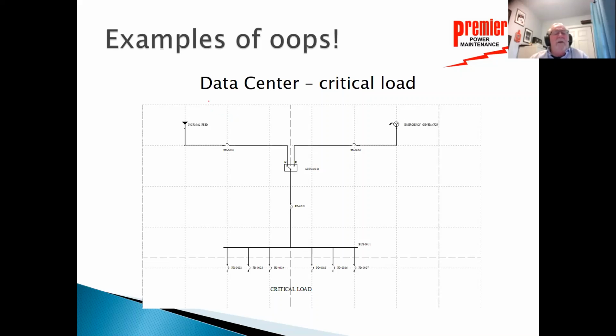It was a data center. It was a large data center. In this data center, they had a utility feed over here. They only had one utility feed because it was located in a little isolated area, but they had an enormous UPS system to feed their facility. And that UPS system was built to withstand a 40-minute outage. And they had an emergency generator here that could carry the full load of the system. Wow, looks rock solid again. Main breaker for the UPS, main breaker for the generator, automatic transfer switch that they maintained and tested on a quarterly basis. Here, what happened? They built the system and all of a sudden they kept adding load.